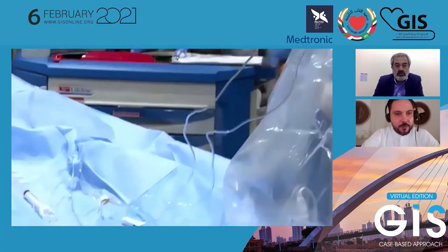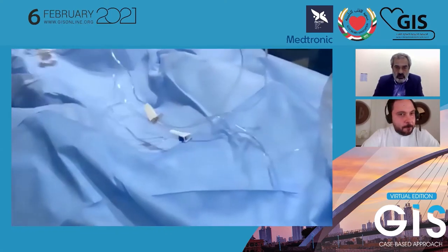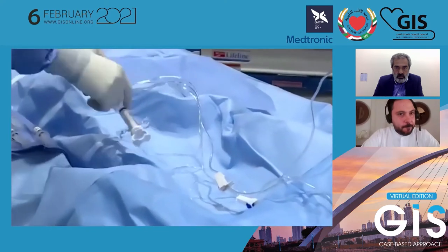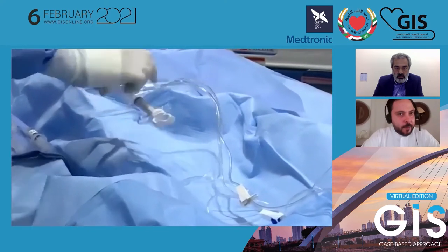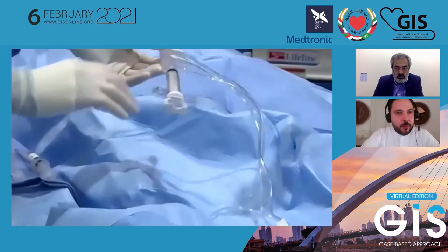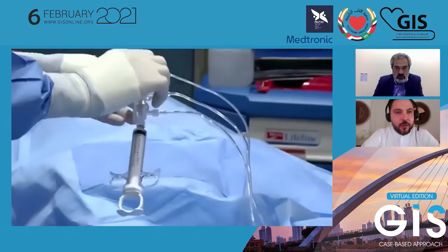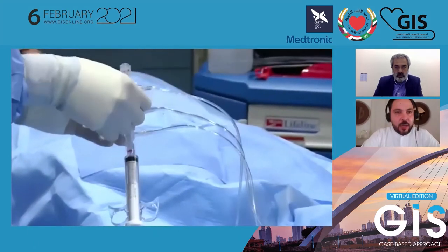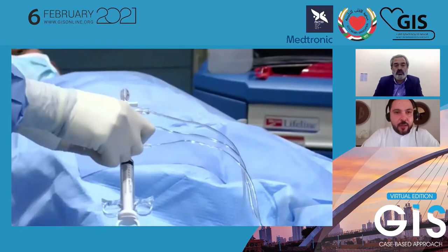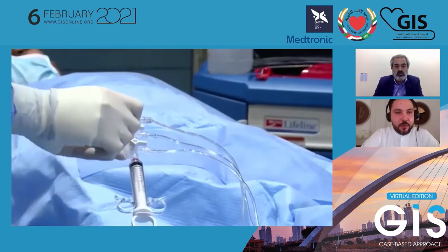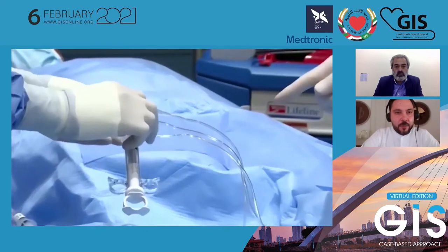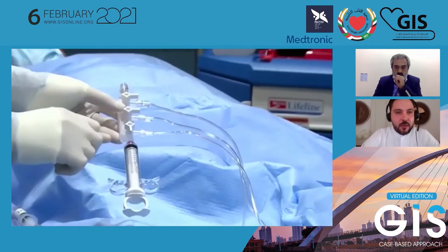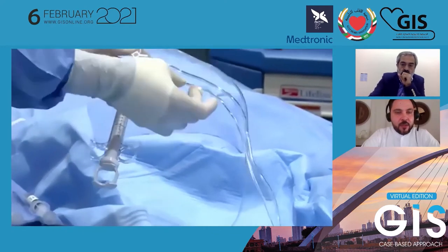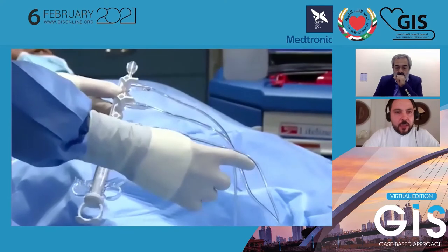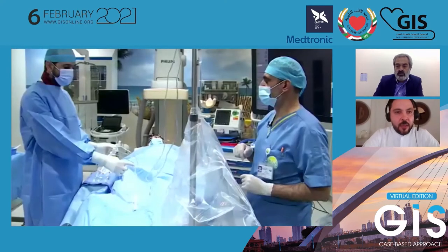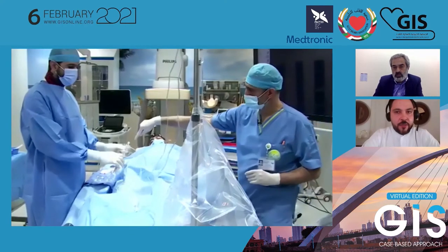First of all, what's usually the troubleshooting that you face when connecting your transducer? Sometimes if it's not flushed well, they have to reflush it again, especially if there's any air bubble. Sometimes during the flushing, if there is any water leaking to the transducer, it will not give you a good reading.